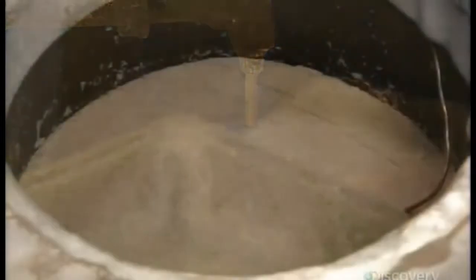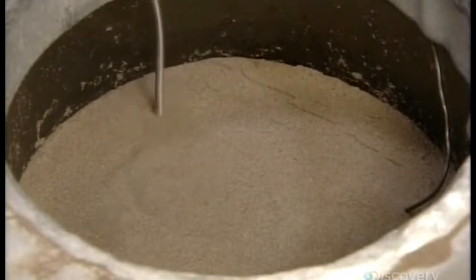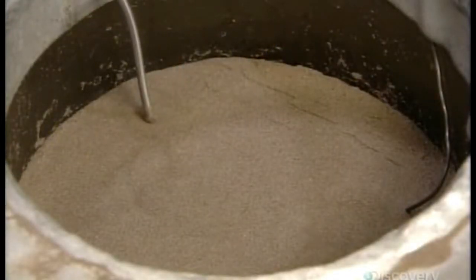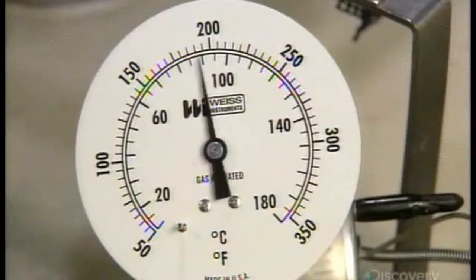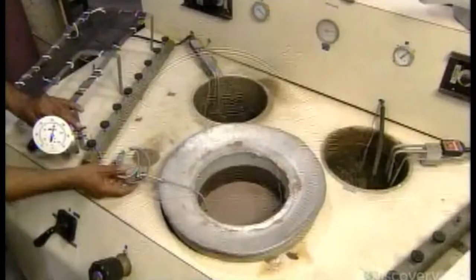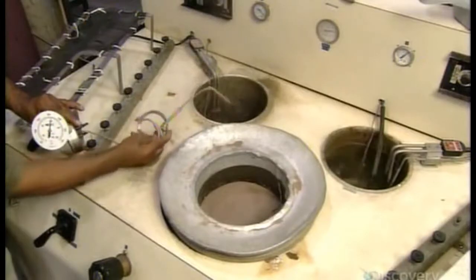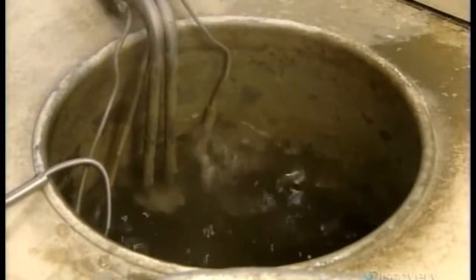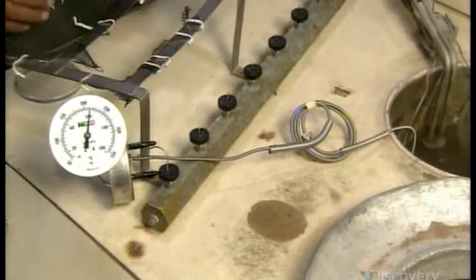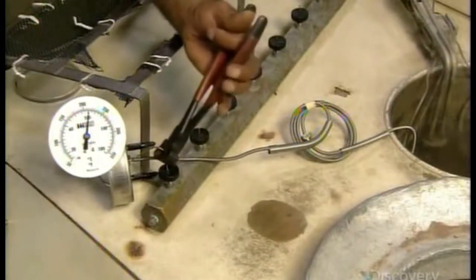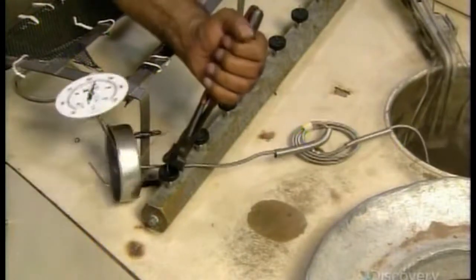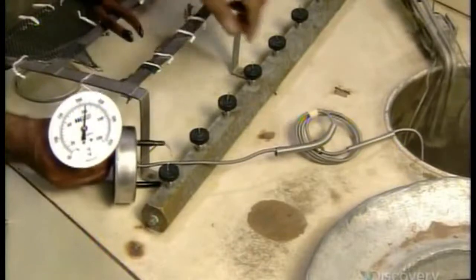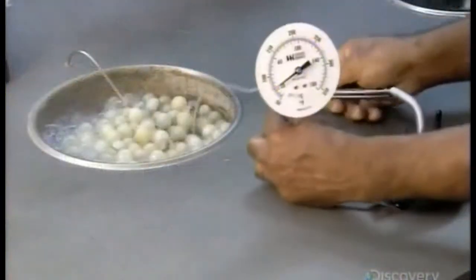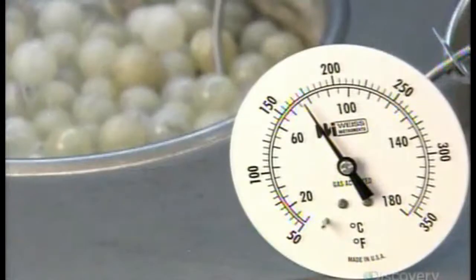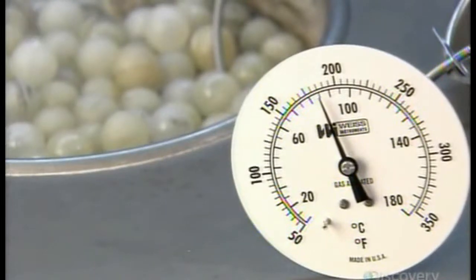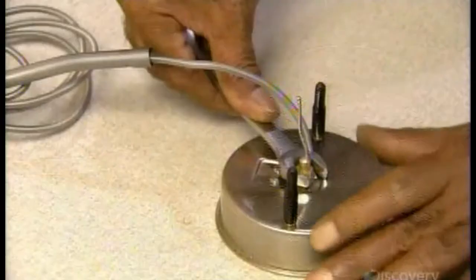He buries the bulb in a hot sand bath, which causes any moisture in it to evaporate. Through the fill tube, he fills the bulb with nitrogen gas. To calibrate the thermometer, he plunges the sensing bulb into boiling water and adjusts the pressure of the nitrogen gas until the dial reads 100 degrees Celsius. The fill tube's job is now done, so he crimps it to seal it off. He tests its accuracy by immersing the sensing bulb in numerous controlled baths, each one a different temperature.